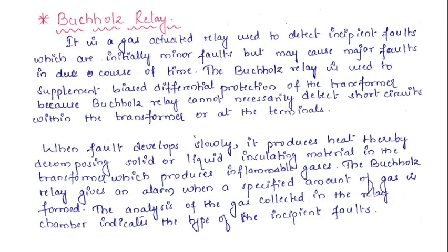So that is the basic operating principle of this Buchholz relay. As and when a fault develops in the transformer, heat is produced because of these faults, decomposing the solid or liquid insulating material. Whatever the insulating material, it may be oil. Here basically we'll be dealing with the liquid insulating material, oil, in the transformer, which produces the inflammable gases. Because of the decomposition of these insulating materials, gases are formed.